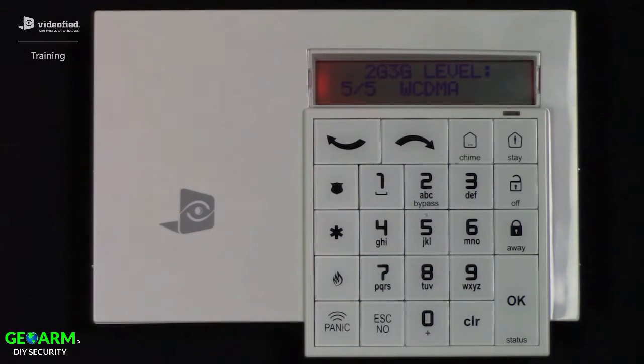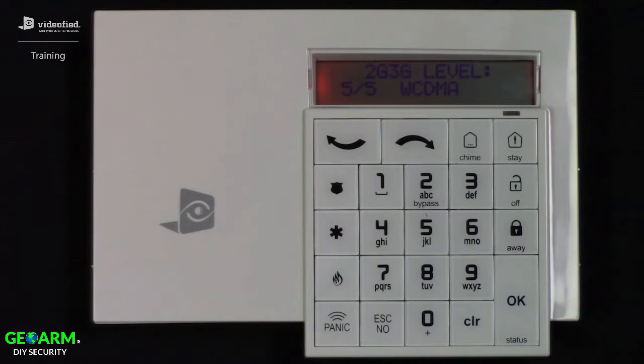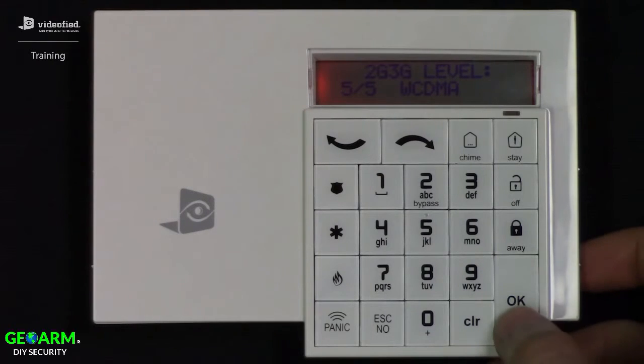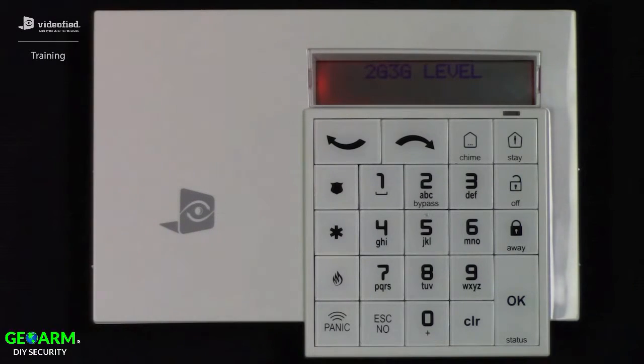The minimum result on the cell test should be no less than 3 out of 5. If the result happens to be less than 3 out of 5, this could actually prevent videos from successfully transmitting to the monitoring station. To exit the 2G/3G level test, simply press OK or the escape/no key, which will bring us back to the maintenance menu options.